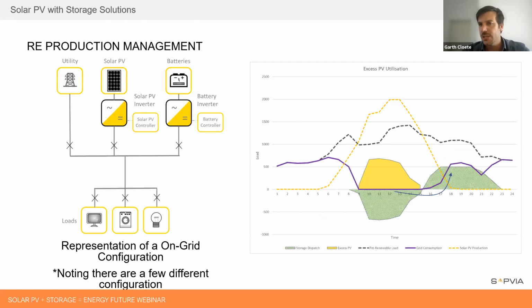Typically, most sites around the country, without exporting significantly and having a normal grid-tied solar PV system, we can impact say a 30-35% renewable fraction. If you want to create a higher renewable fraction without wasting excess energy into the utility grid without any returns, we start oversizing the PV.